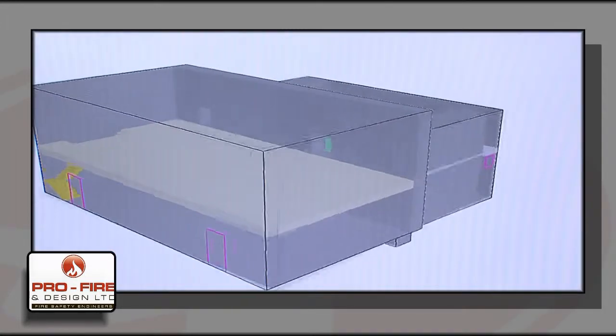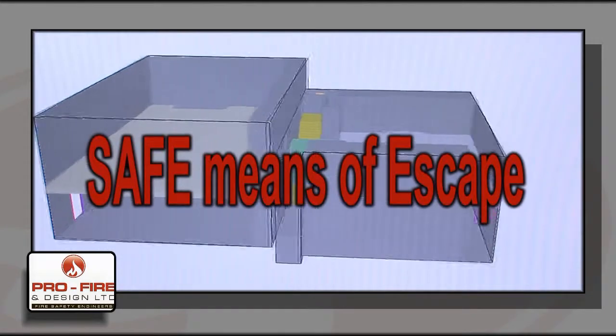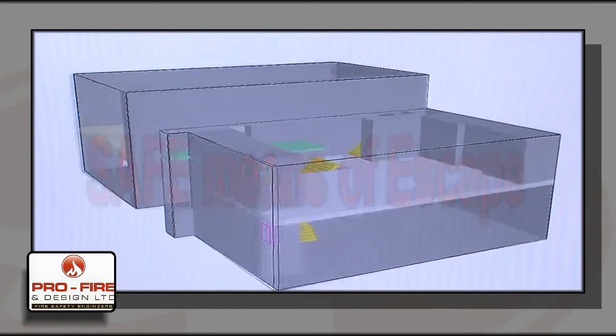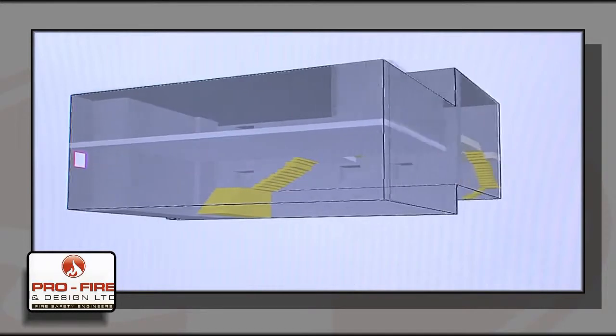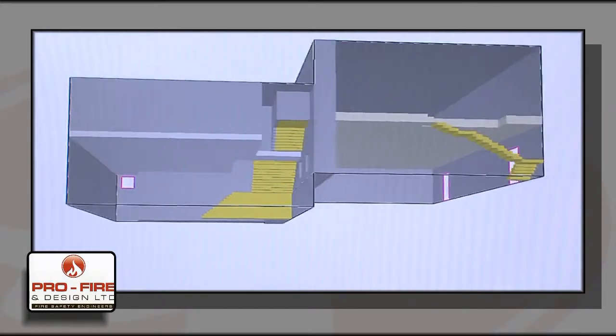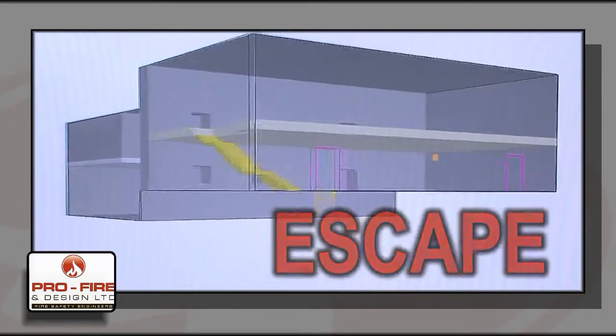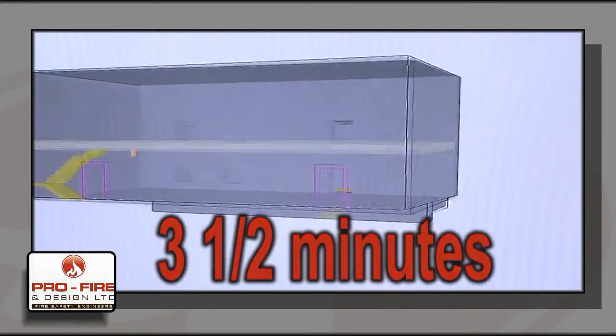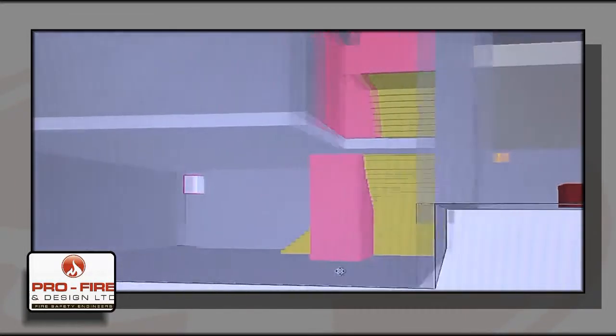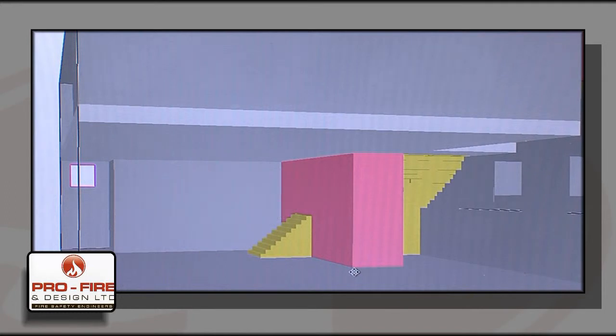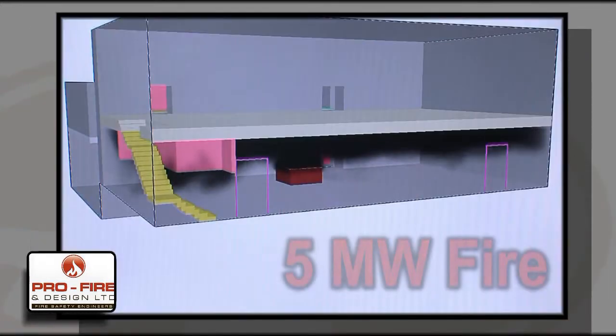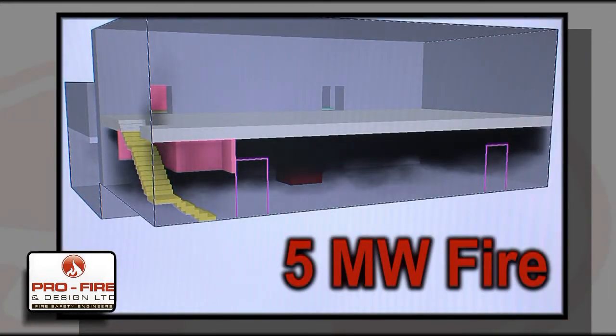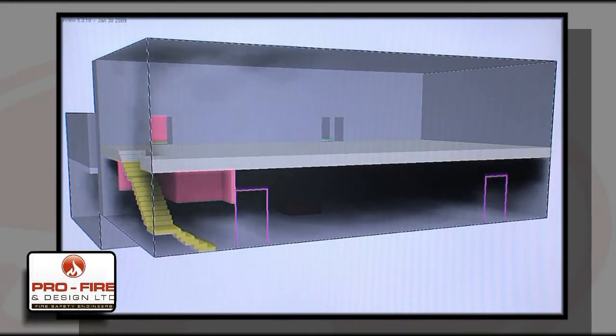Profire developed a CFD simulation to illustrate that safe means of escape would be maintained for a minimum of 8 minutes, when calculations determined that the time for occupants to react and then escape would be approximately 3.5 minutes. The strategy involved the use of smoke curtains and smoke extraction fans. We simulated a 5 megawatt fire within the lower level of the church area.